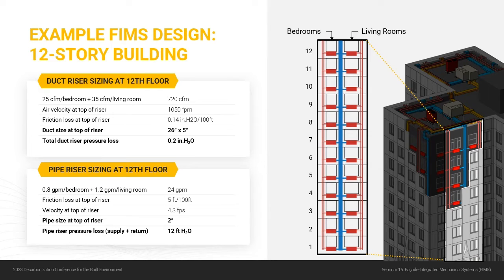Now we're going to do just a quick example design, just so you can see what some of these numbers actually look like when you apply this to a building. We'll start by looking at the sizes of the risers. This example building that we'll be using is a 12-story building. So if we look at a duct that's going from the top to the bottom of the building, serving 12 floors, we're being conservative here.